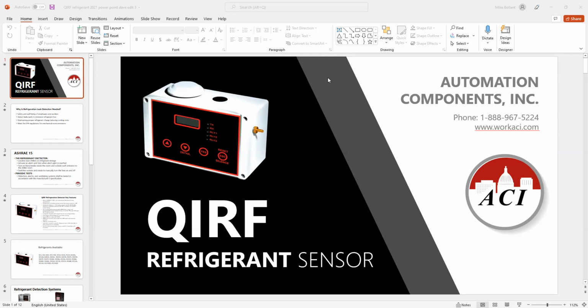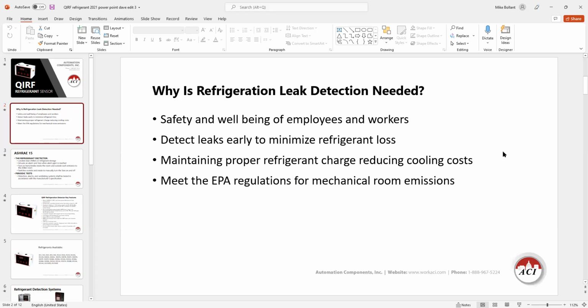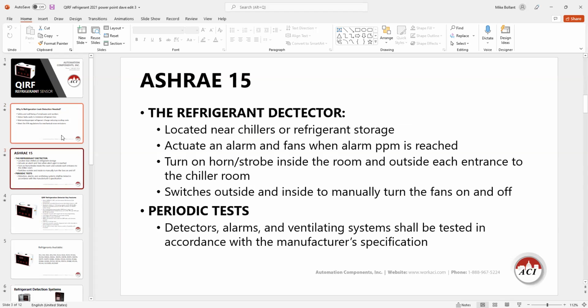So this is our Freon detection system for basically chiller plants, and QIRF is our refrigerant detector. I'll, of course, get into details on that in a couple of slides. We know why Freon is needed in chiller plants. We abide by the ASHRAE 15 for the most part for refrigerant detections, and we'll have some network diagrams. I'll explain how the system works together in a few minutes.